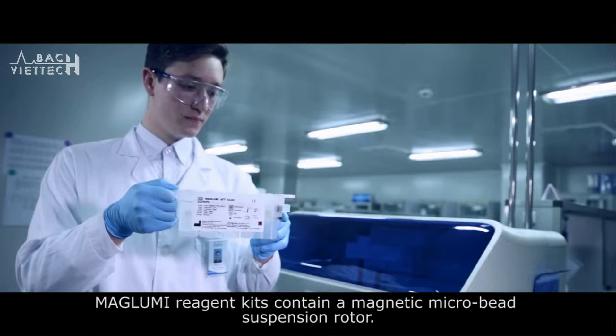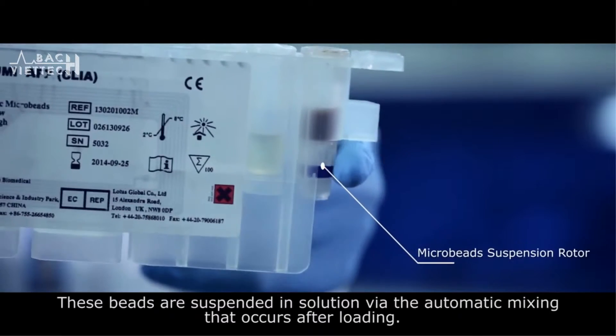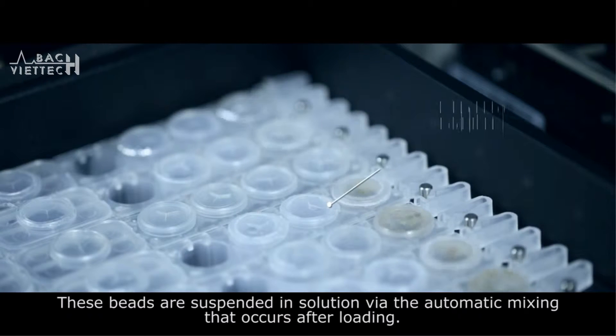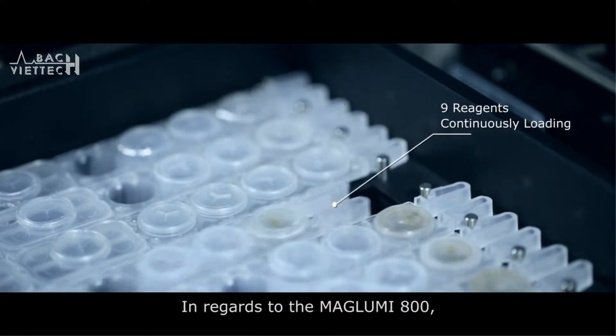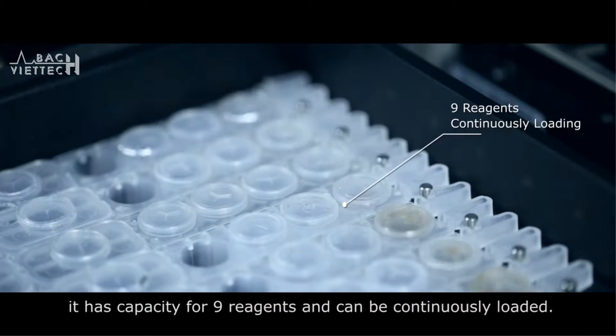MAGLUMI reagent kits contain a magnetic microbead suspension. The microbeads are suspended in solution via automatic mixing that occurs after loading. The MAGLUMI 800 has capacity for 9 reagents and can be continuously loaded.